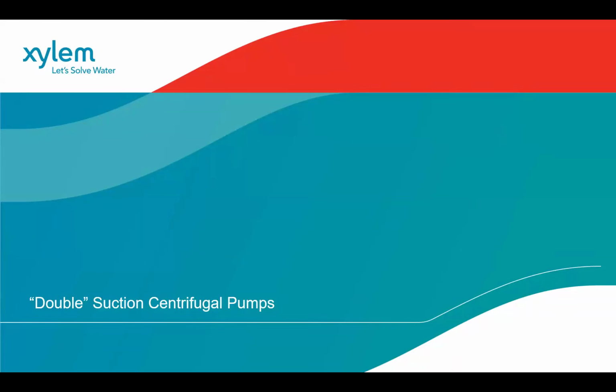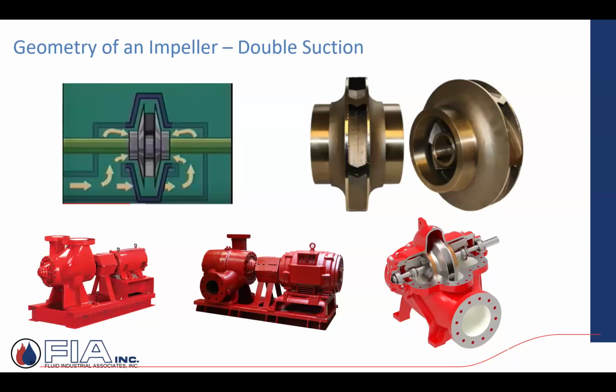This last section of centrifugal pumps I just want to touch on is referred to as the double suction centrifugal pumps. Just as a description, those were single suction impellers, these are double suction impellers. As this drawing is trying to show, water will actually enter both sides. There are two eyes to this double suction impeller. So it enters the right-hand side here, and it enters the left-hand side.